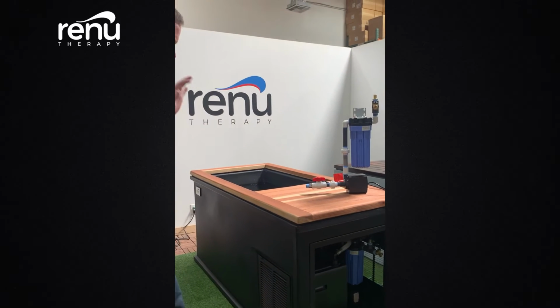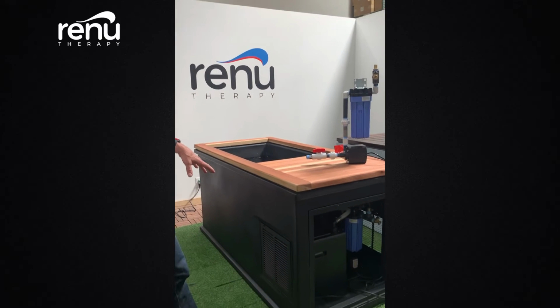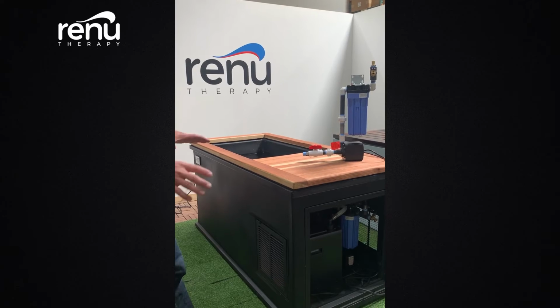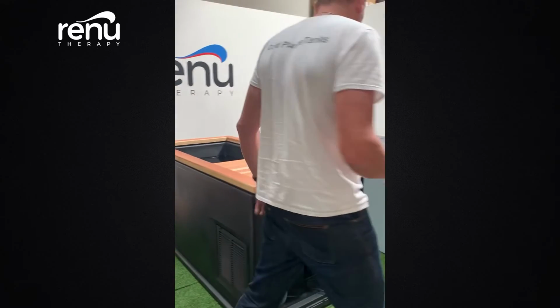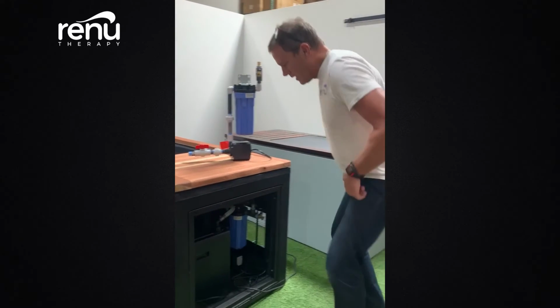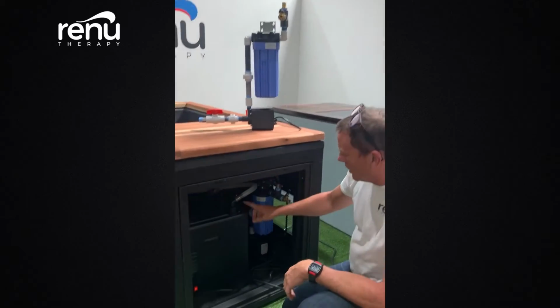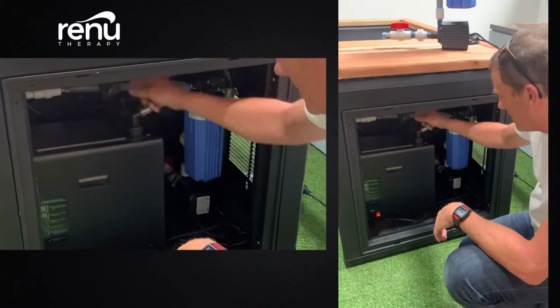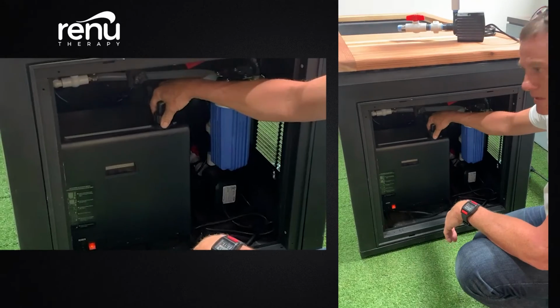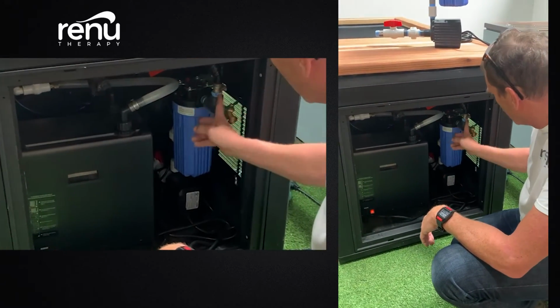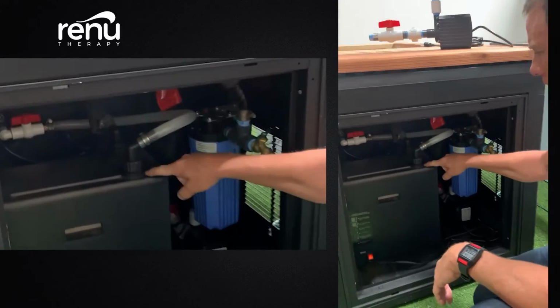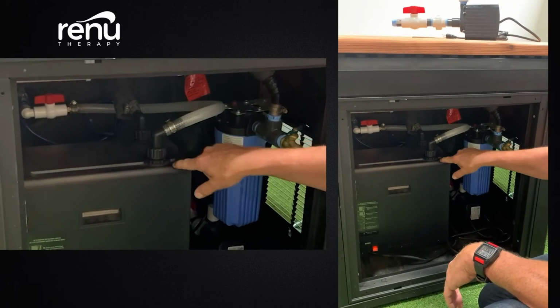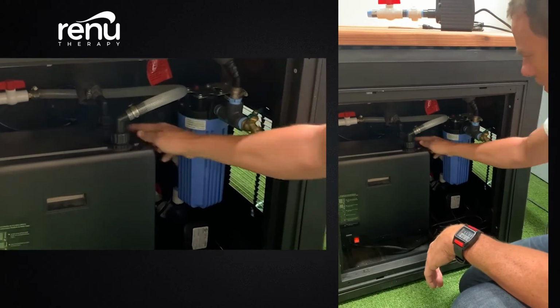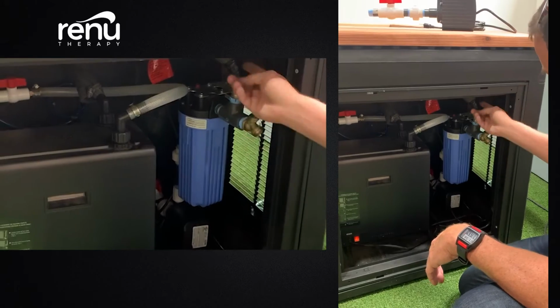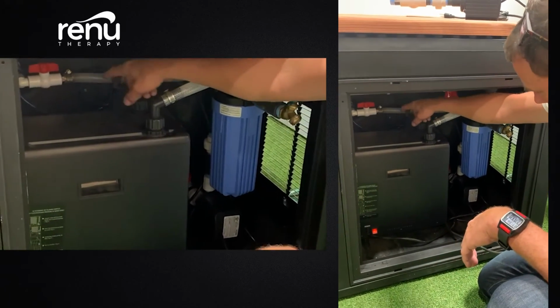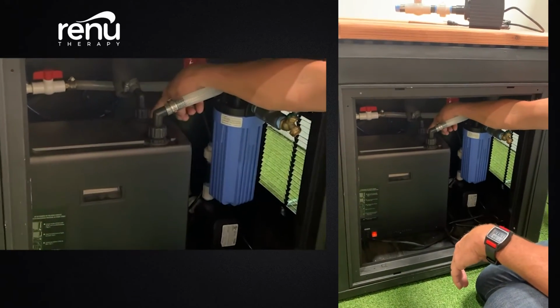If you've adjusted the temperature on the chiller and it's still not doing it, then you want to just confirm that you have a fresh filter in, and you want to make sure that your hoses are in the right position. Sometimes people will accidentally switch the hoses up. The one that comes off the filter housing has to go in where it says in. There's a little in button here and a little out button here. So this goes in, and the one that goes to the tank will be coming from the outflow.